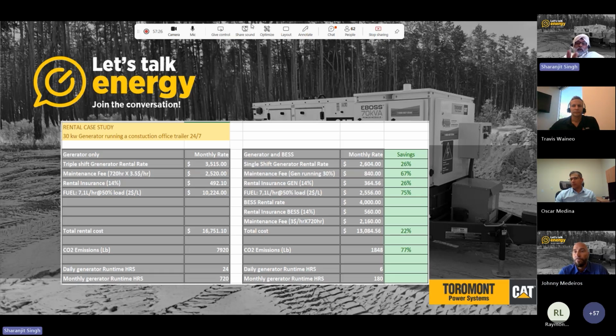Thank you very much, Johnny. So in this particular case, using the BESS, the generator set was running at its optimum efficiency, high loads, rather than at lighter loads as in the case on the left-hand side. Also want to clarify that the CO2 emissions figure is a calculated number, not a measured number for that case, right Johnny? Correct.